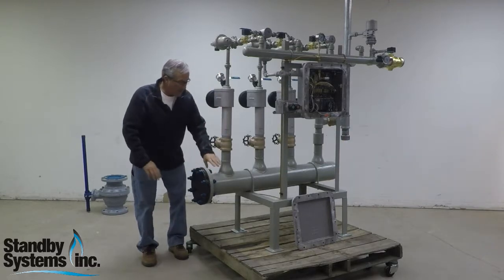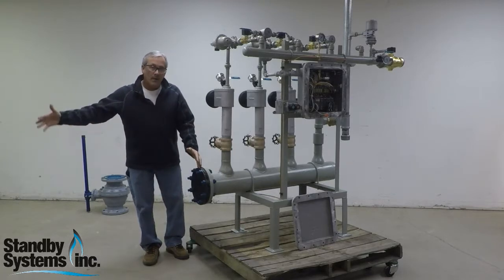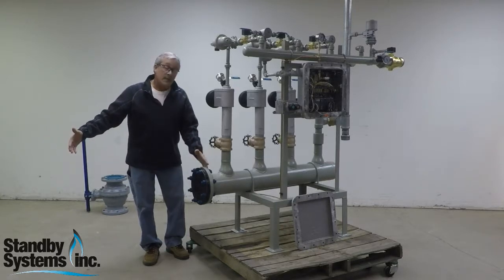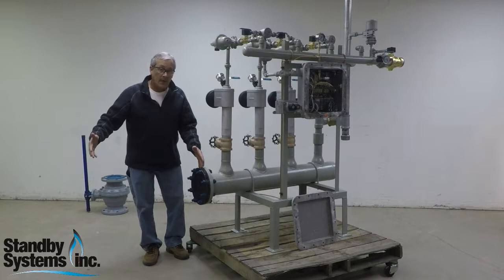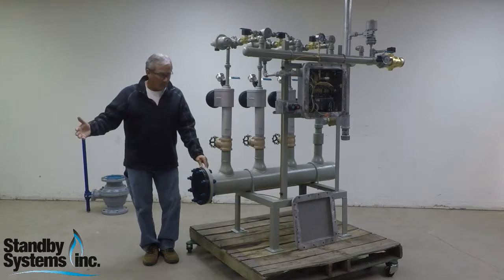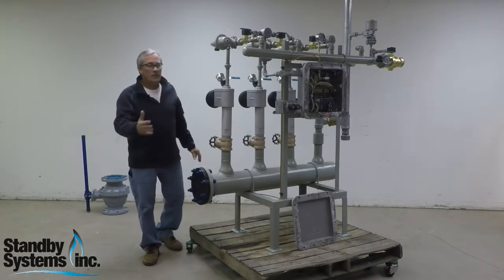This comes down into this header. This unit is made to have an additional surge tank, or as a replacement unit for an existing mixer that has a surge tank. The surge tank is really just a receiver tank, very much like what you'd have on an air compressor. That's just not shown on this unit because it's usually used for replacements.